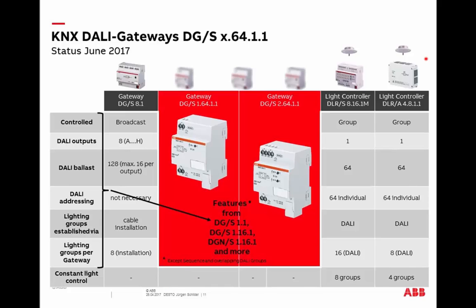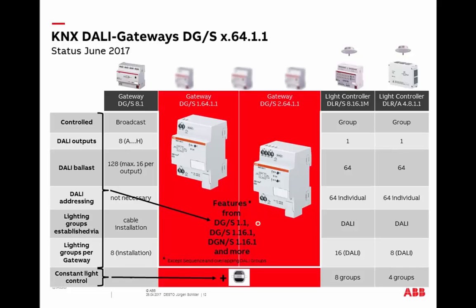Constant light control is not directly integrated in the new gateways — we can still use our existing components DLRs or DLRA. But another option for constant light control is to use our KNX presence detectors: the premium version has an integrated light sensor and constant light control software, and you need only a further dimmer to create a complete solution. This is already done frequently using our existing DALI gateways, and of course it is also possible with the new ones.